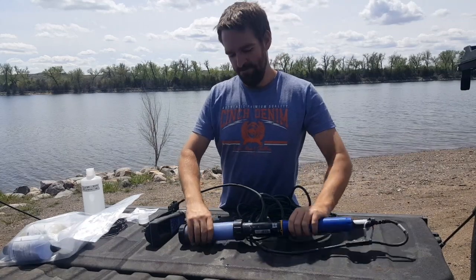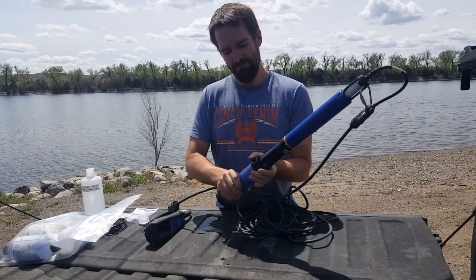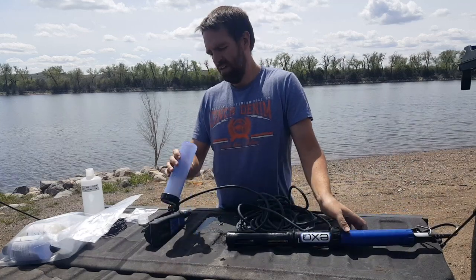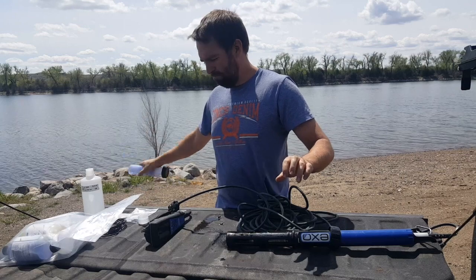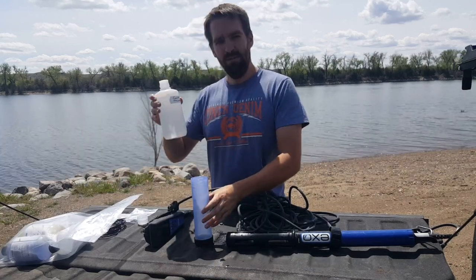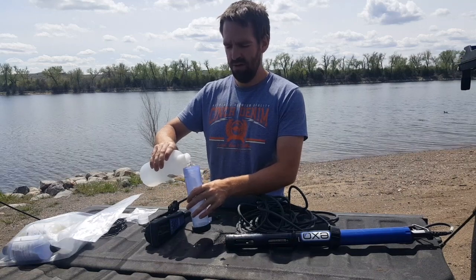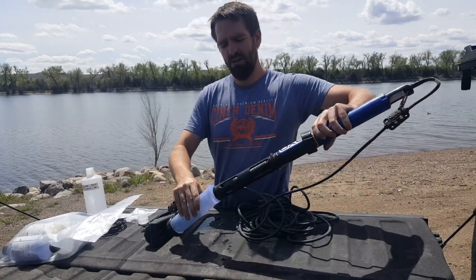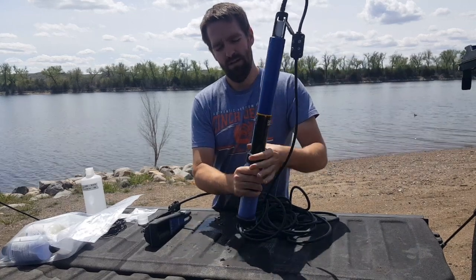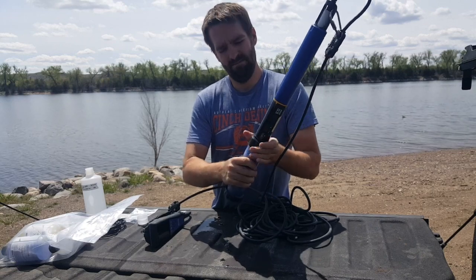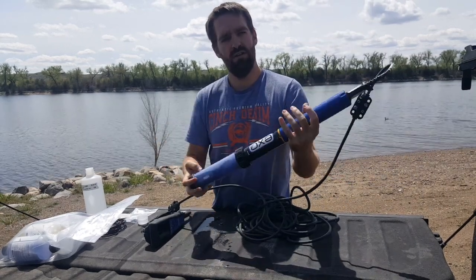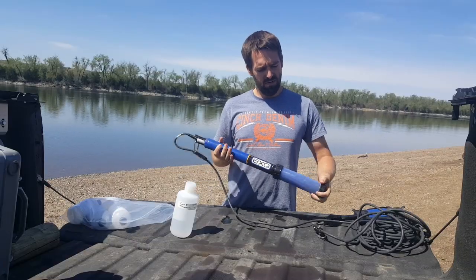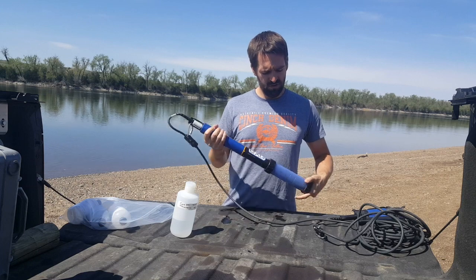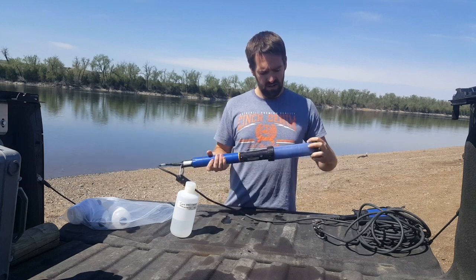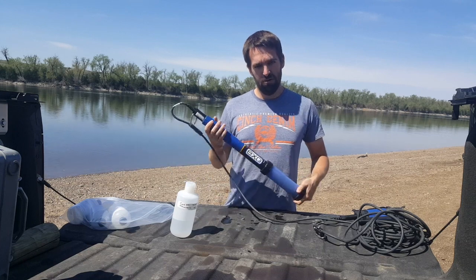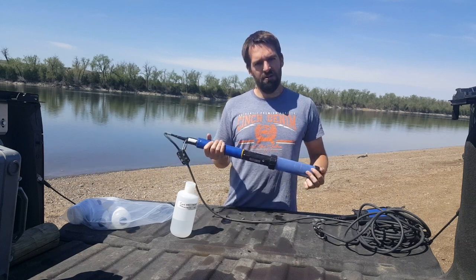Okay, first we're going to start with conductivity. So what I do, I'm going to take off my cup, discharge any leftover water that's in the cup, take my conductivity solution, just pour a little bit in there, put the cup back on my sonde, tighten the cup back down, and I just gently swish it back and forth. We're going to do a pre-rinse. So what we're doing is we're going to swish just a little bit of conductivity solution to get any contamination that might be on our probes or on the guard. This just ensures that we get a better calibration value.